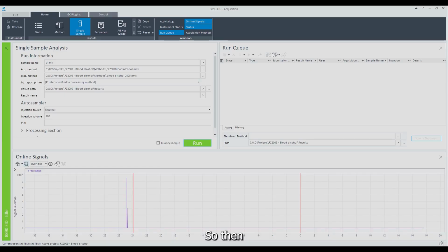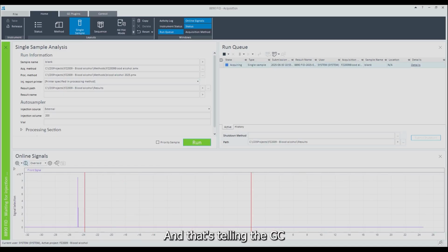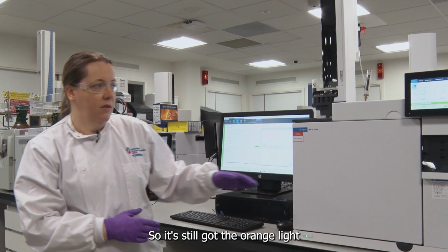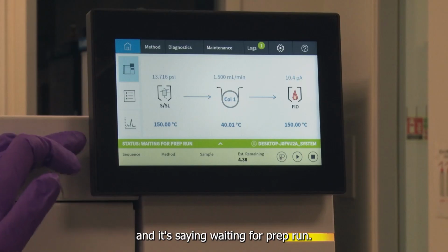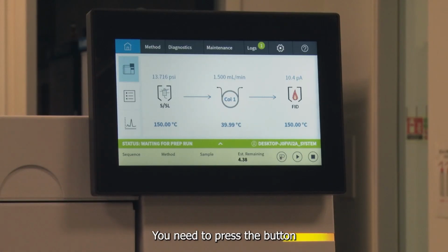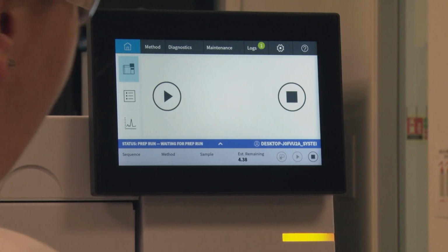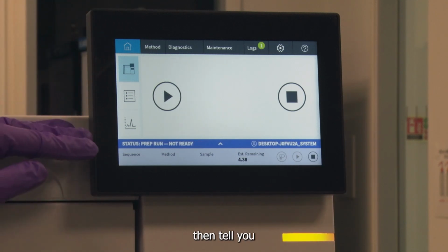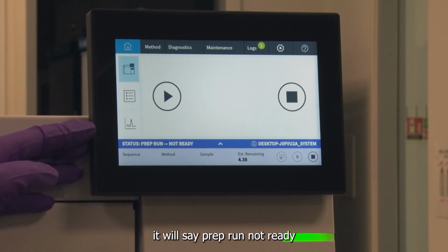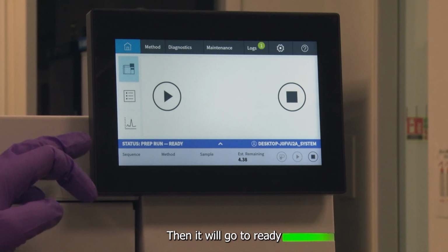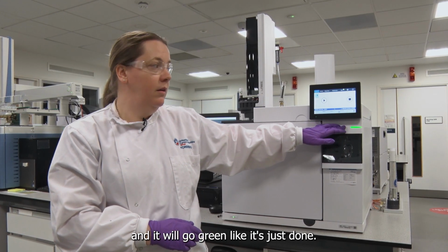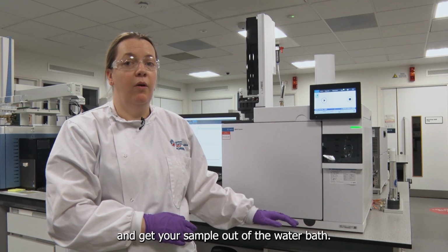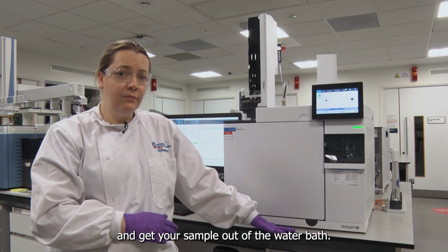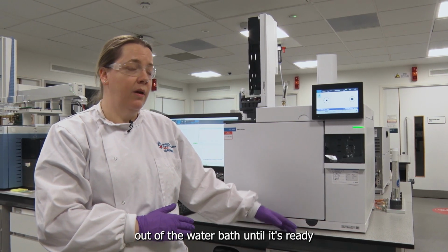So then you click run, and that's telling the GC what the method is and what the sample is going to be. So it's still got the orange light and it's saying waiting for prep run. You need to press the button that looks a bit like a test tube, and this will then tell you when the GC is ready to inject. So initially it will say prep run, not ready, and you'll have the orange light. Then it'll go to ready and it'll go green like it's just done. Now you can go and get your sample out of the water bath.